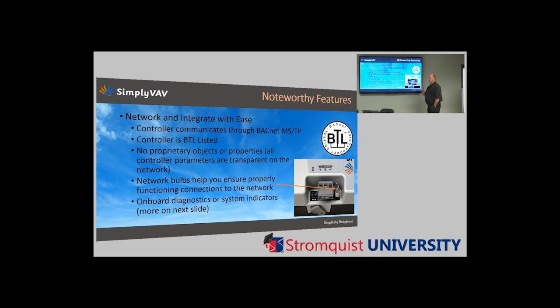BTL, BACnet Testing Laboratories. A lot has been said about BTL. BTL, if you're not familiar with them, they are an independent third-party organization. They're kind of like the Underwriters Laboratories of the BACnet world. Anybody can make a product and say, hey, I'm BACnet compatible, right? Well, the ultimate way for a manufacturer to put his money where his mouth is is to send the product to BTL for that independent third-party testing.